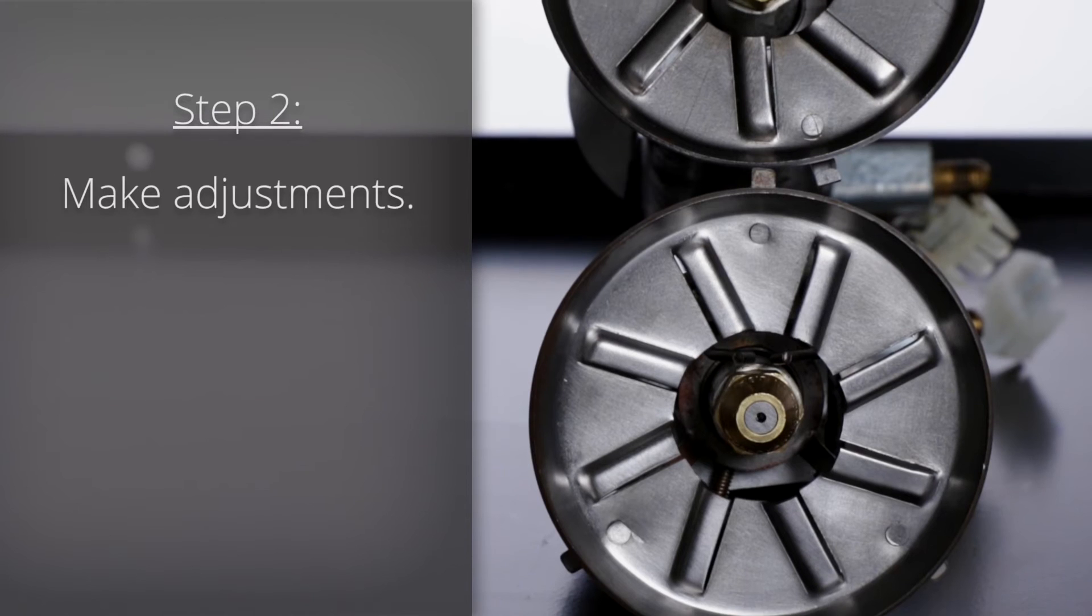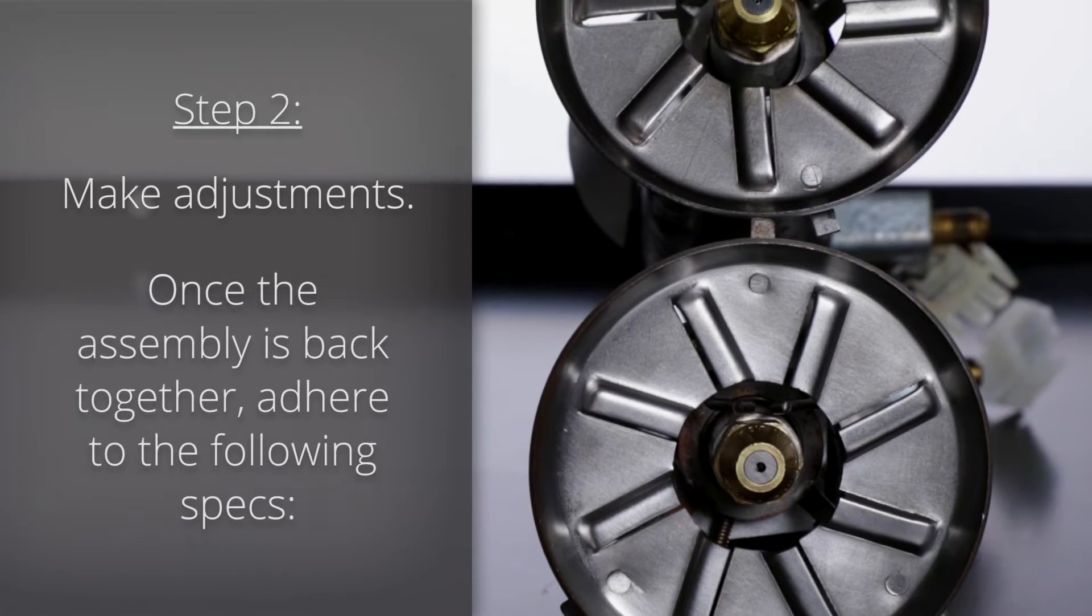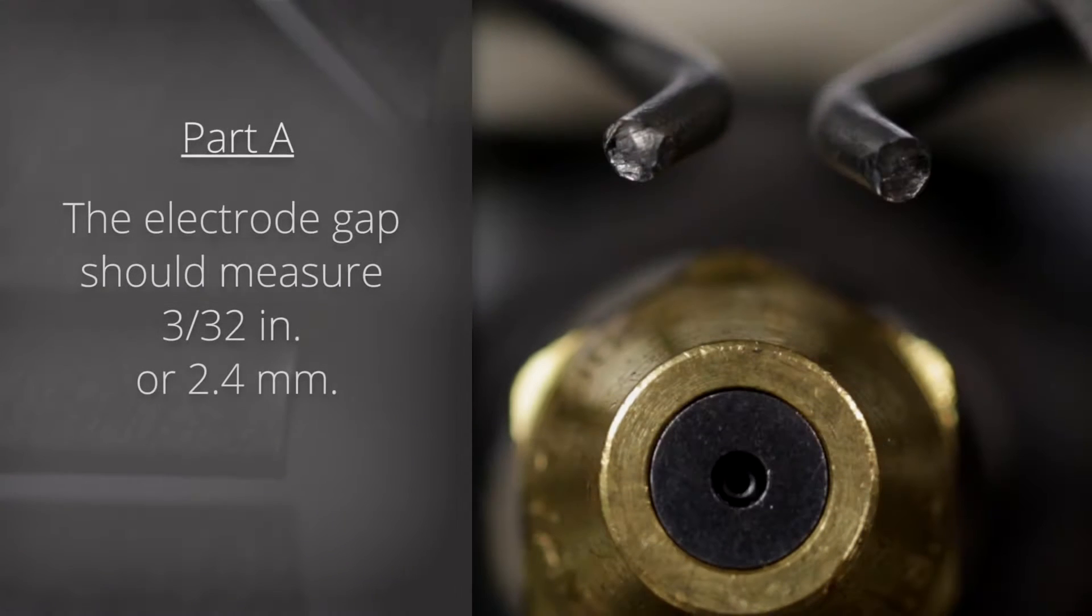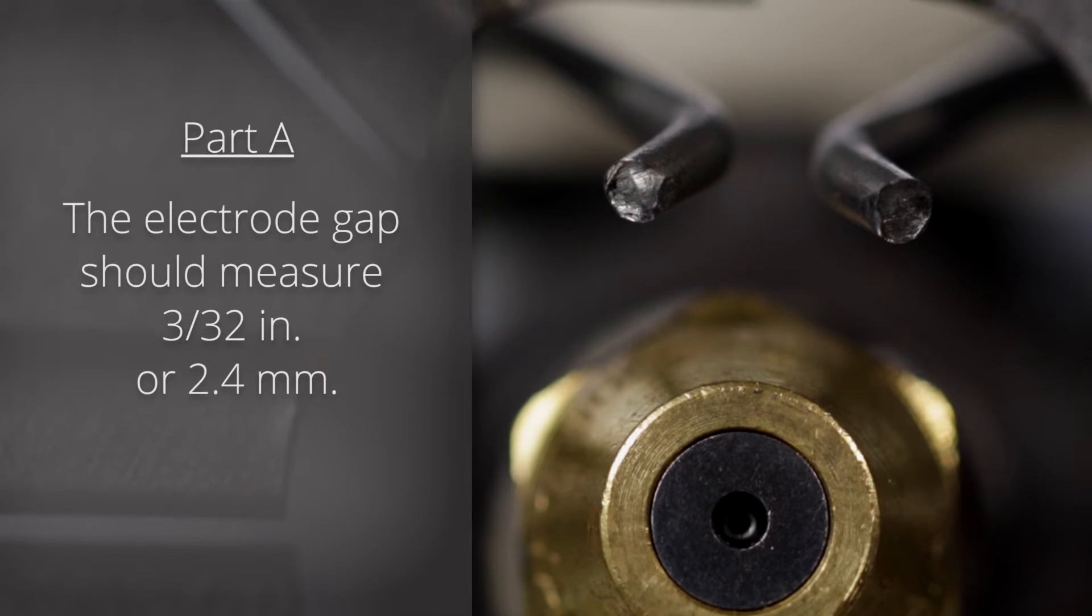Step 2: Make adjustments. Once the assembly is back together, adhere to the following specifications. Part A: The electrode gap should measure 3/32nds of an inch or 2.4 mm.